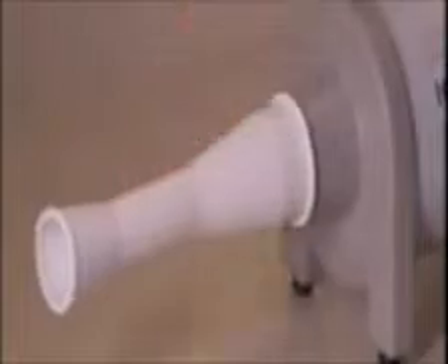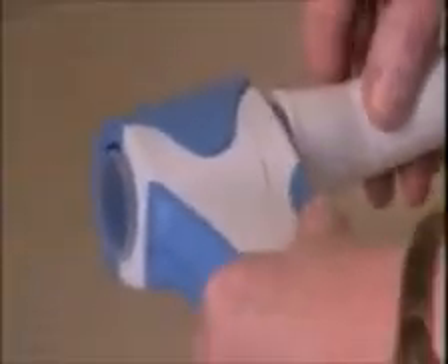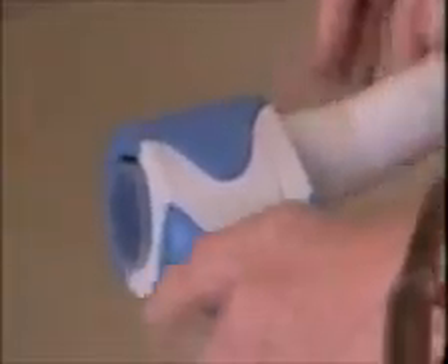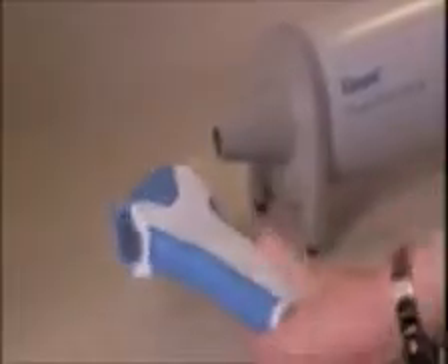Attach the large end of the syringe adapter to the calibration syringe and the small end of the adapter to the disposable mouthpiece that is attached to the spirometer. Never calibrate the device with a syringe that fits inside the disposable mouthpiece. Always use the syringe adapter when calibrating the spirometer. Click New Cal on the calibration screen and click Start Cal. The sensor will zero itself and then the calibration pump screen appears.